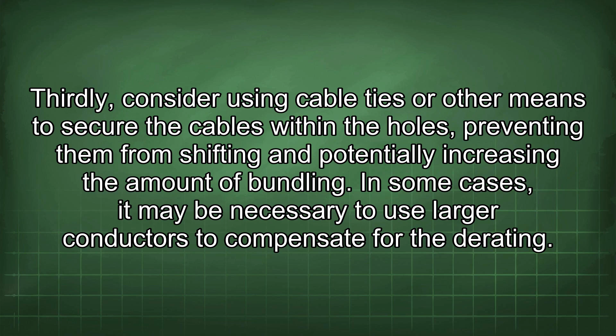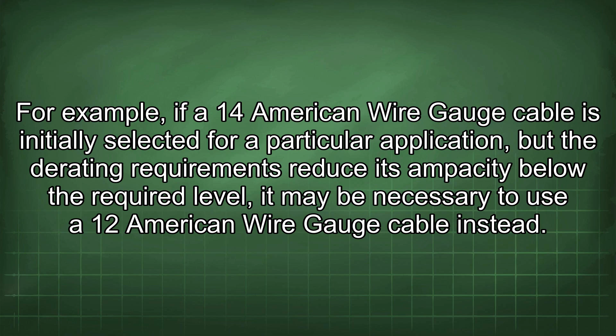In some cases, it may be necessary to use larger conductors to compensate for the derating. For example, if a 14 American wire gauge cable is initially selected for a particular application, but the derating requirements reduce its ampacity below the required level, it may be necessary to use a 12 American wire gauge cable instead. Using larger conductors can increase the cost of the installation, but it can also improve the overall safety and reliability of the electrical system. Another option is to use cables with higher temperature ratings.